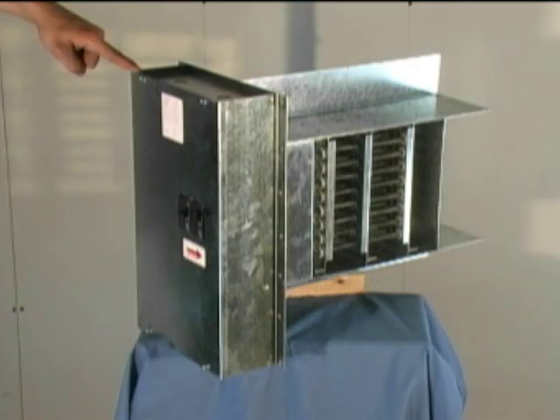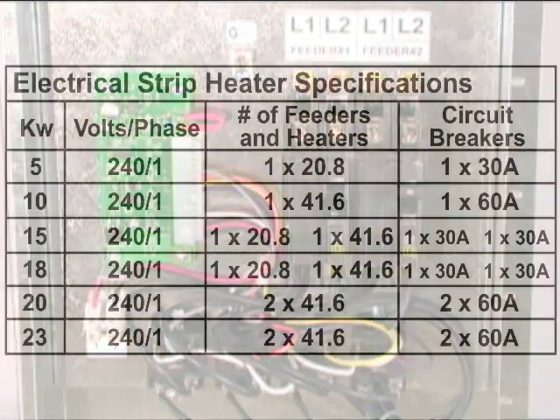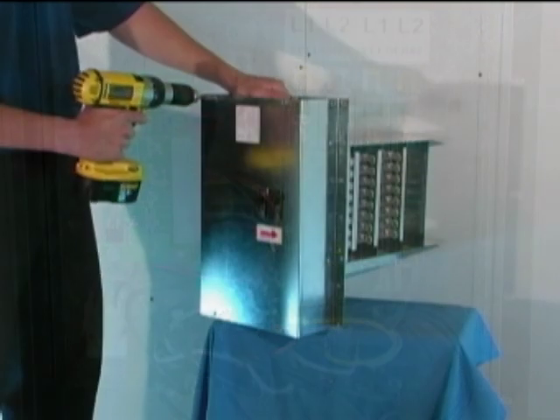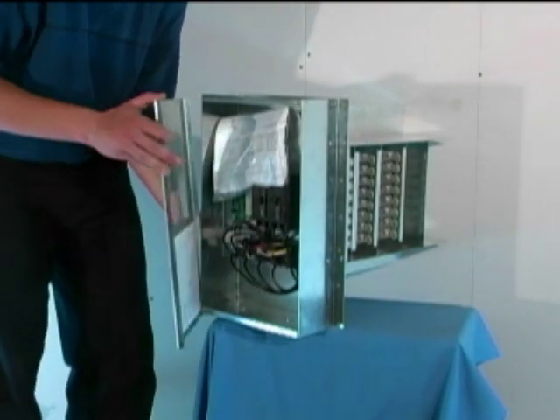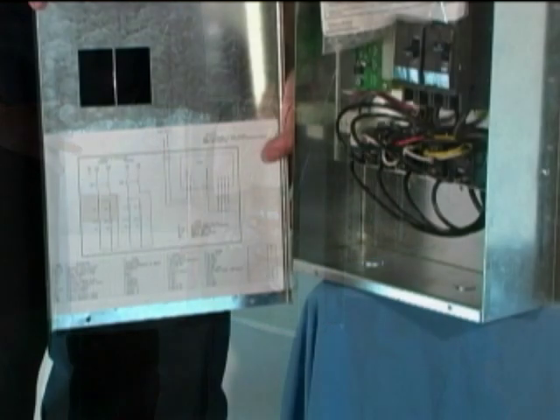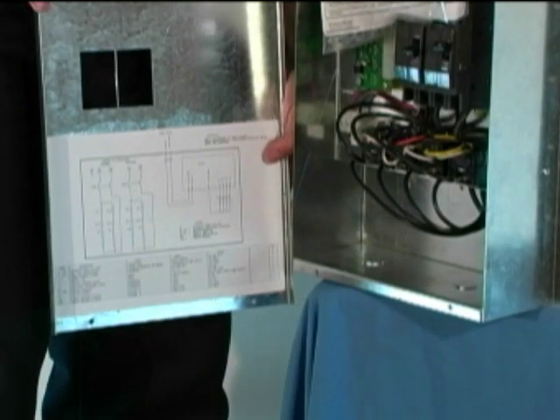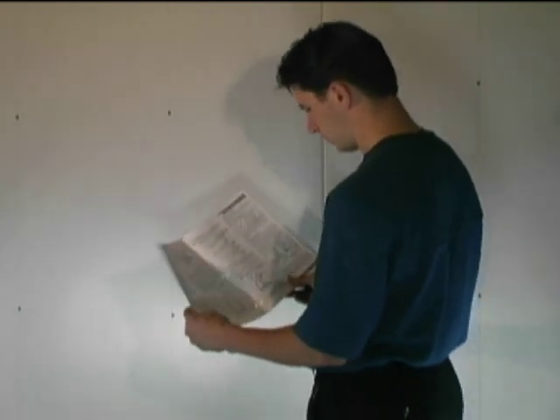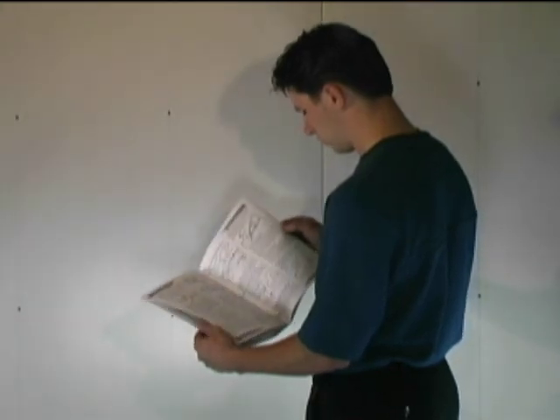The electric coils require 240 volt single phase connections, and the amperage can range from 30 to 60 amps depending on the model being used. With all the power sources disconnected to the electric coil, remove the access panel. The wiring diagram is on the inside of the electric coil access panel, or refer to the installation guide. All wires shall be run and sized in accordance with local electrical code laws.